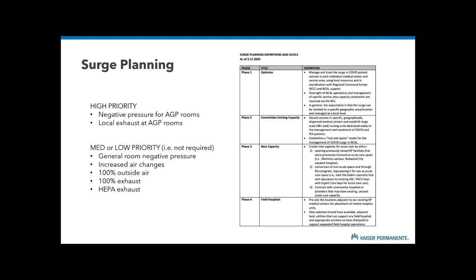To summarize this first white paper, the big emphasis was to facilitate surge planning. My department, the architects I work with, the planners, had this insane task. I remember one of our leaders saying, it took us 50 years to get the bed count we have in Kaiser Permanente, you have 60 days to double that, go. And we did, we actually have surge plans for every hospital for those bed counts. It's kind of crazy. But if engineering had said you have to convert every room to negative pressure, every system to 100% outside air, HEPA filters in every room, those surge plans would have become way more time consuming, way more expensive, way harder to execute. We need to be valuable, we need to be prudent, we need to be practical, and I think this white paper achieved that.